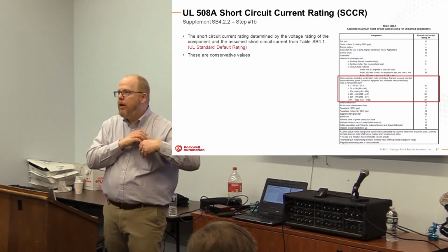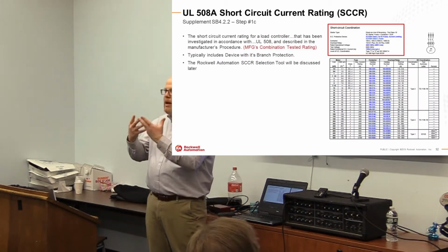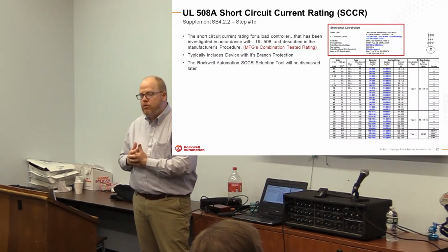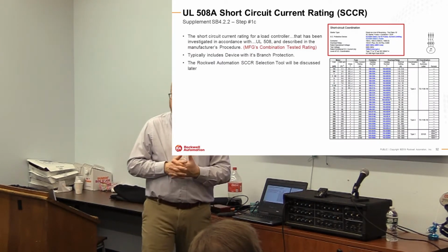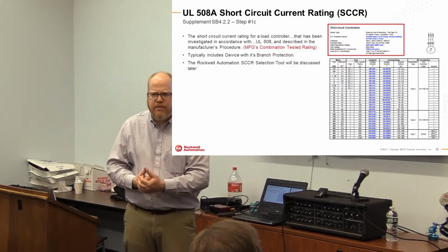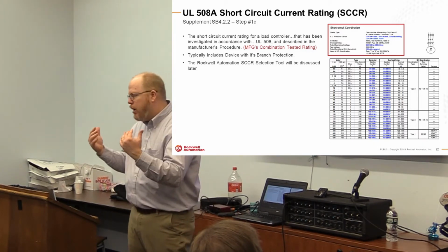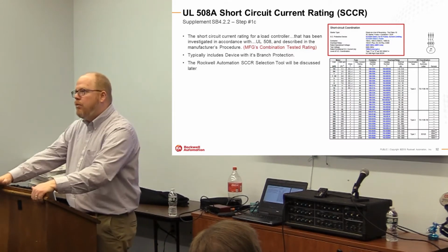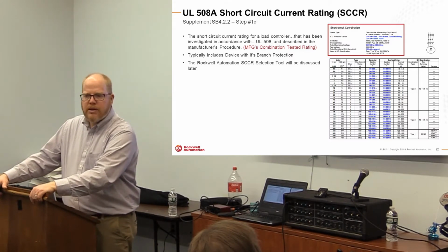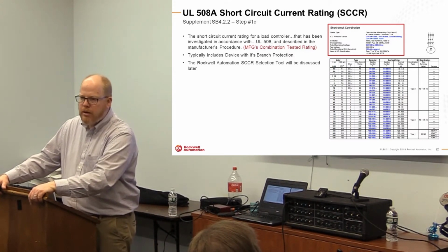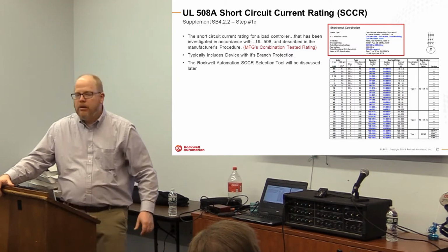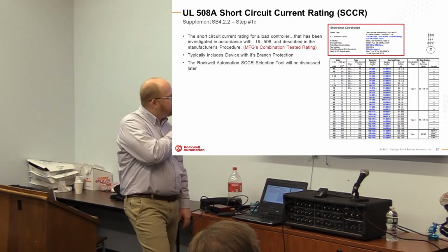And then the third one is an illustration here. This is an example from our short circuit current rating tool of a manufacturer combination test rating. And competitors would have the same, Schneider, Siemens, whomever, where we test a combination of a contactor with an overload relay with a circuit breaker, fuse, and whatnot. Okay, so one of those 3 bits of data is what you need.